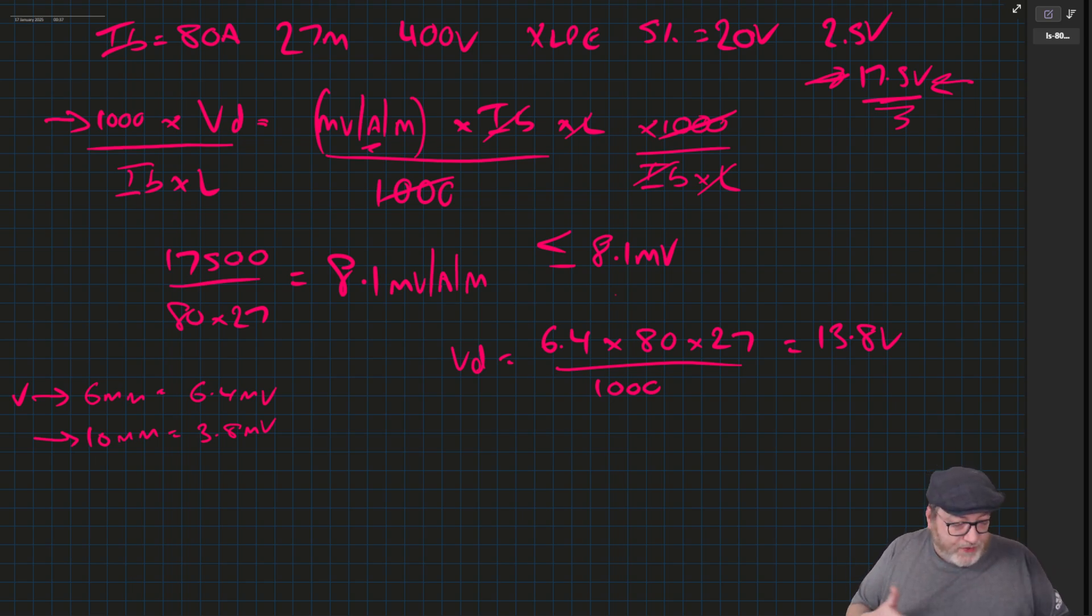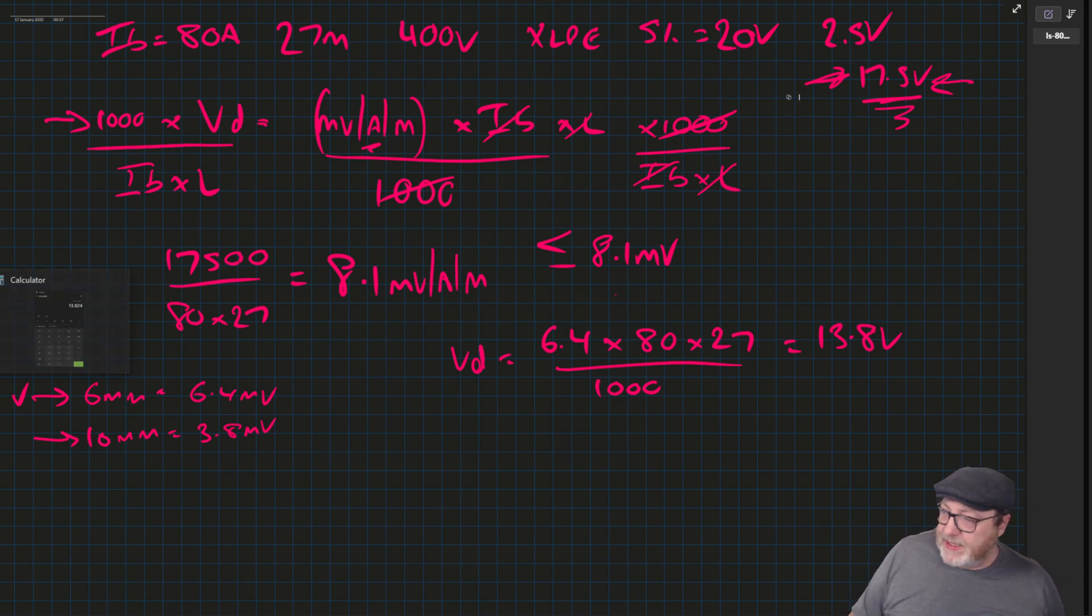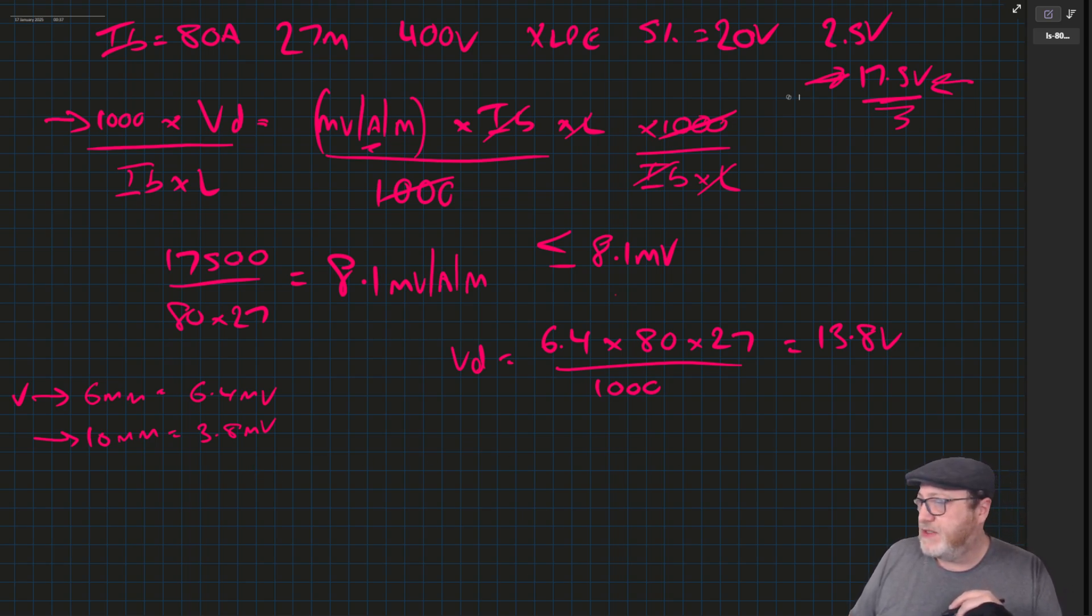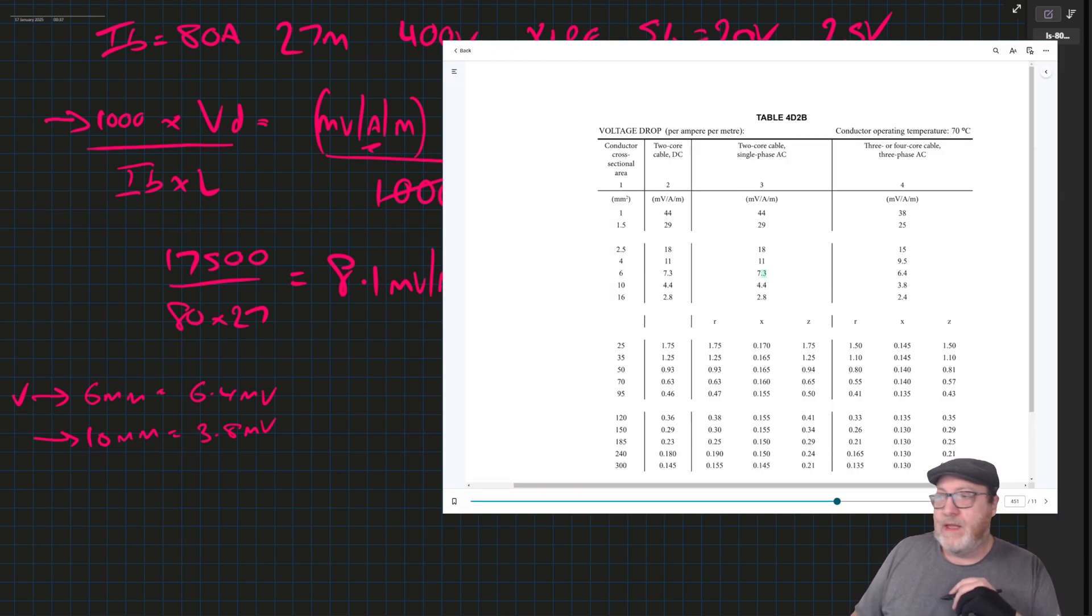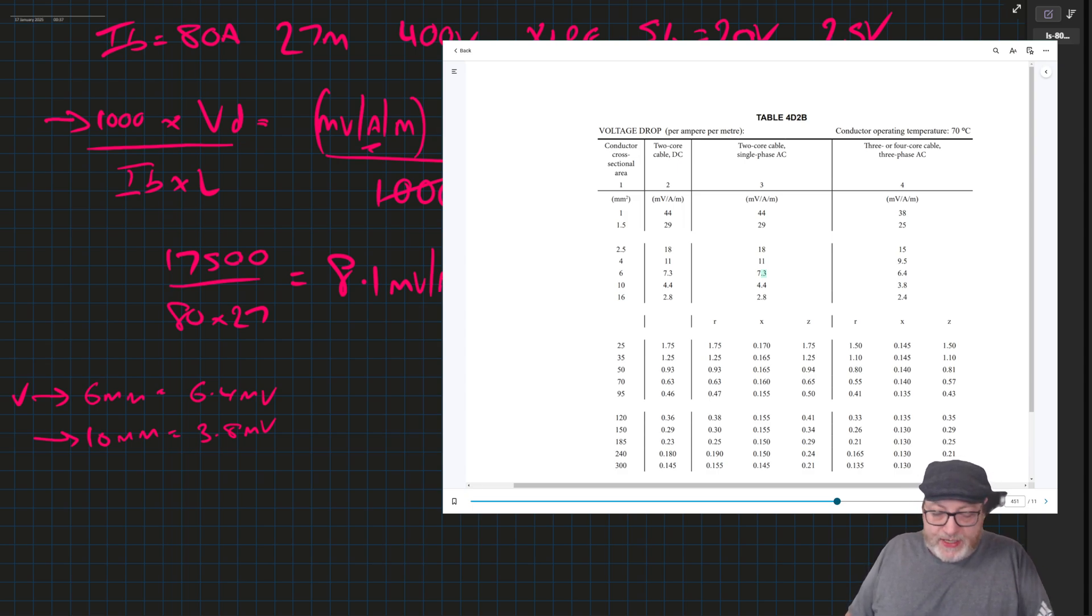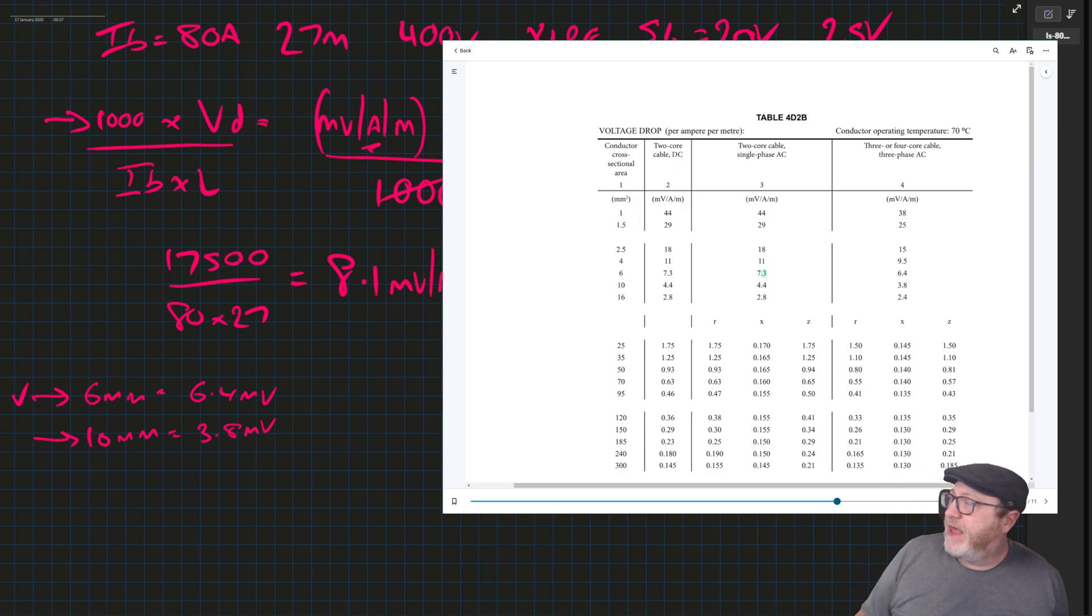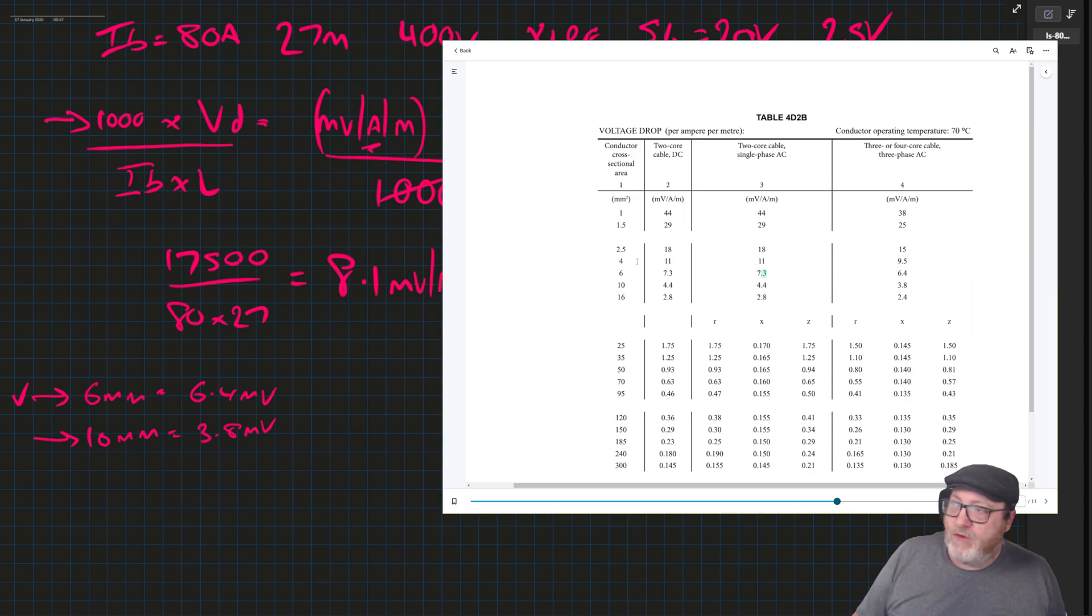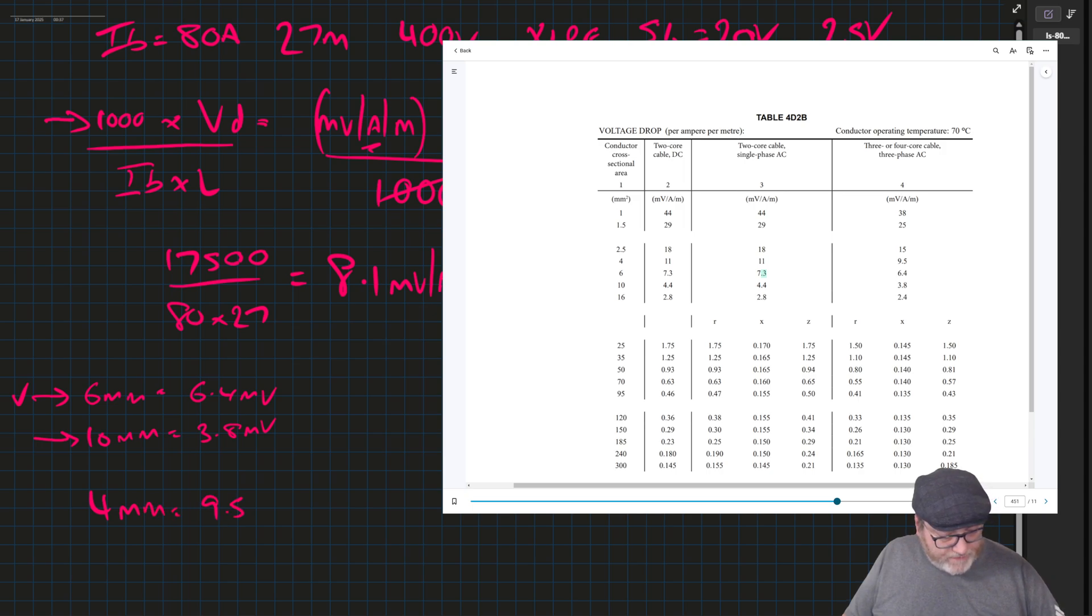If you try 10 mill, you're obviously going to have even less volts. So just for completeness, and it's always a good idea to do this for completeness, is let's go back to that table where we found the 6 mill. We calculated that we had an 8.1 millivolt maximum. So let's look at the cable that's over that. The 9.5 here, that belongs to 4 mill. So let's play with the 4 mill. 4 mill equals 9.5 millivolts.